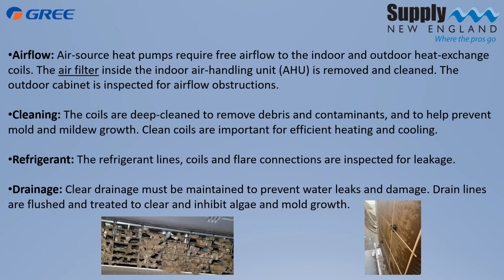We're going to check that refrigerant line, make sure that nobody's kinked the line, that the weed whacker hasn't cut off our insulation, that nothing's been destroyed or disturbed. We're going to be checking for any signs of oil near our fittings to make sure that the unit doesn't have any leaks. And then we're going to put a condensate tablet in there to clean our drain lines. I like to put my condensate tablet on the opposite end of where my drain is, and that way as the condensate tablet melts, it's working that entire drain line all the way through the pan and into the drain hose itself.